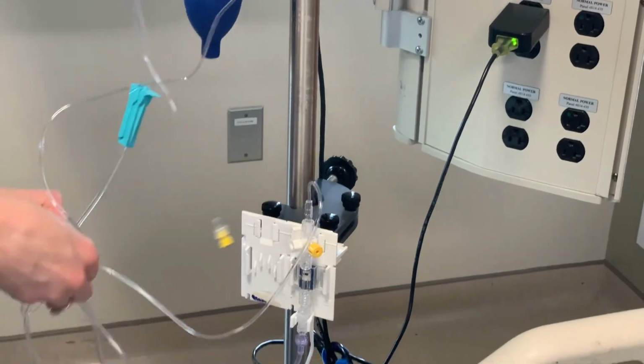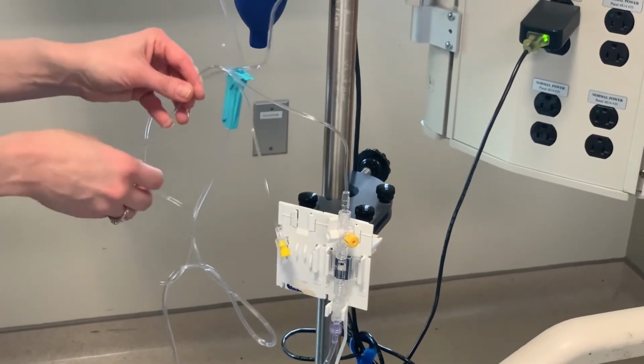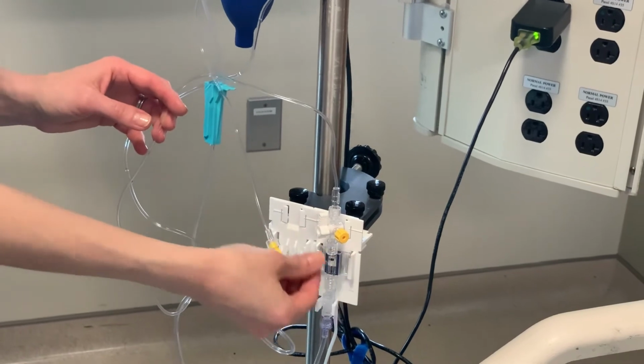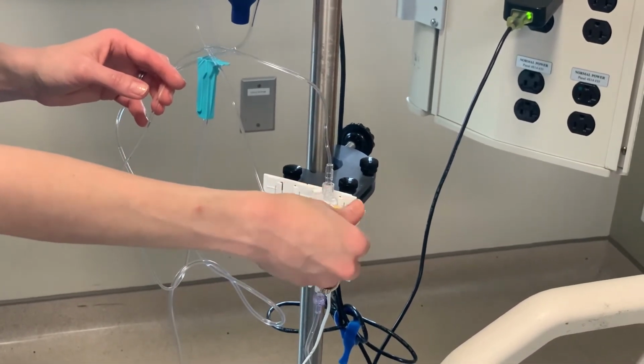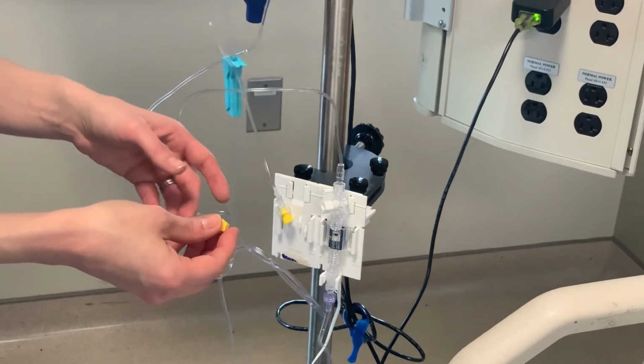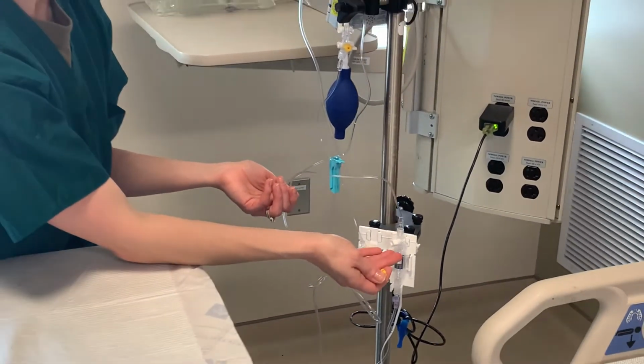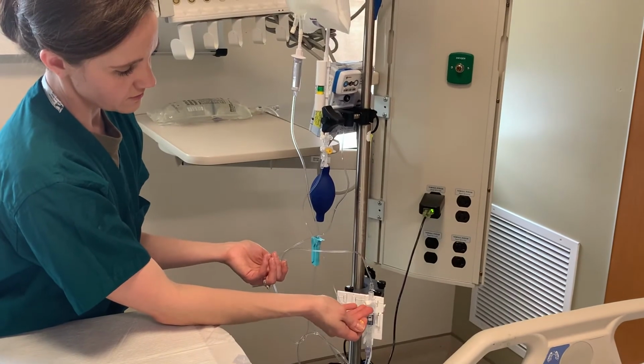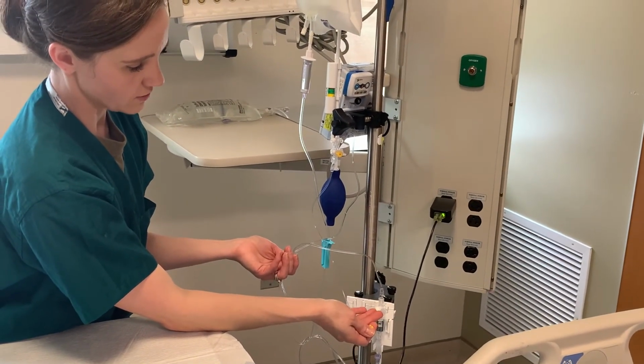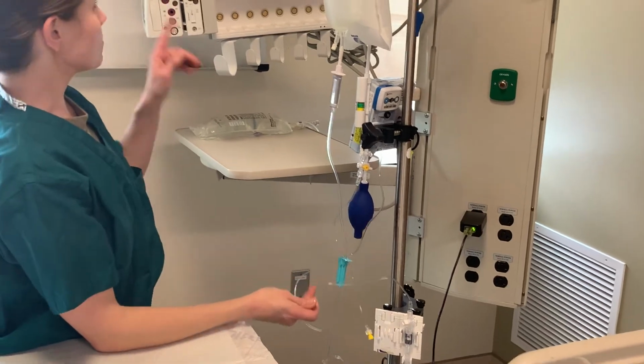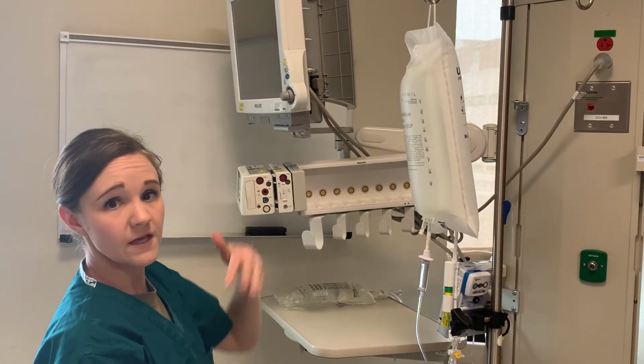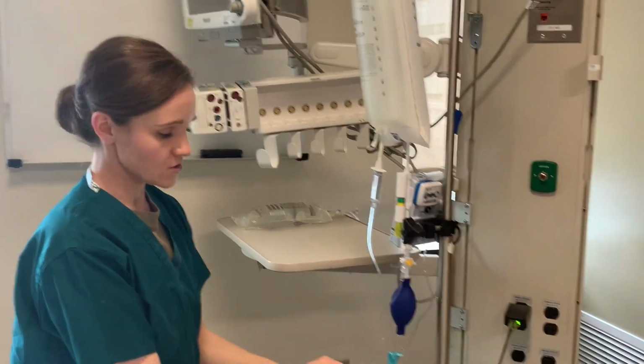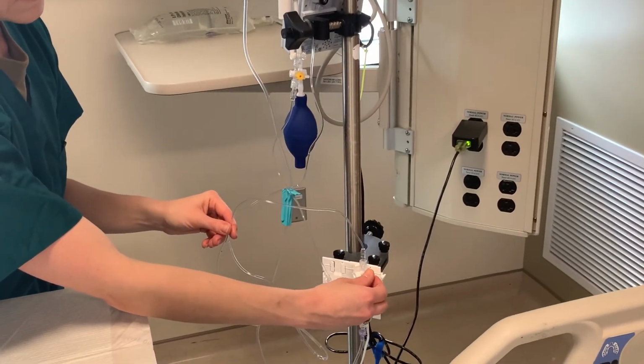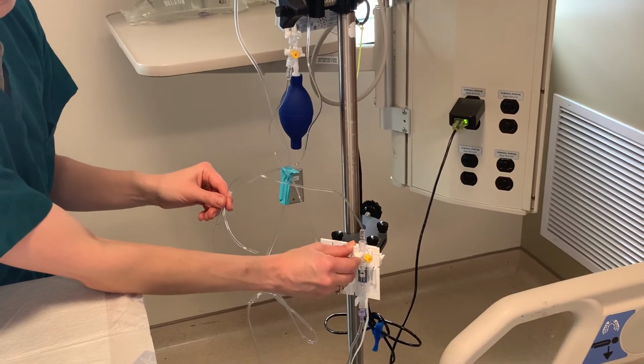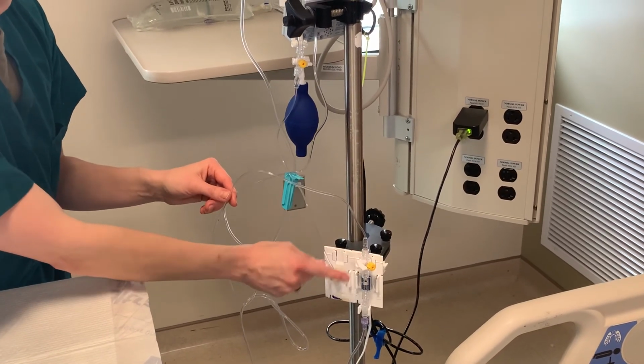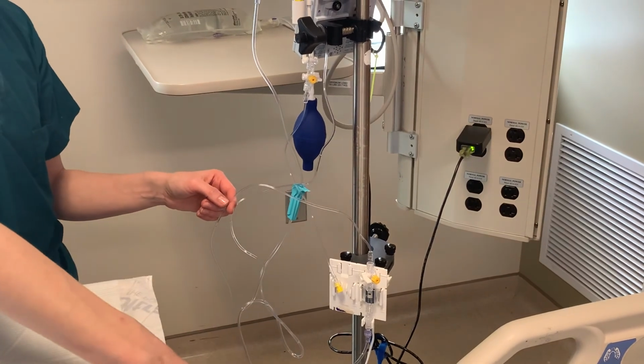This rigid tubing will be going to the patient, so you don't want to zero to the patient, obviously. You will turn it off to the patient. You will open your port here. This will now be open to atmospheric air. This is where you want to zero your arterial line or your CVP. So after you open this, you will go to your monitor, you will select zero, and you will see the zero pop up. Once that happens, you can come back, put the cap back on, and you will turn the stopcock off to the port, and now the transducer is reading the patient's waveform.